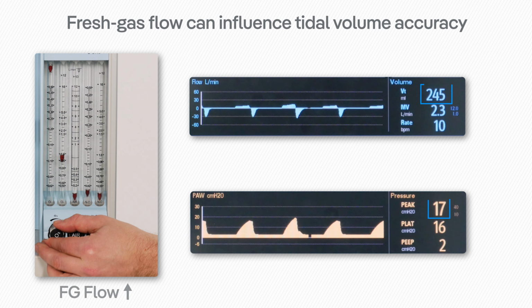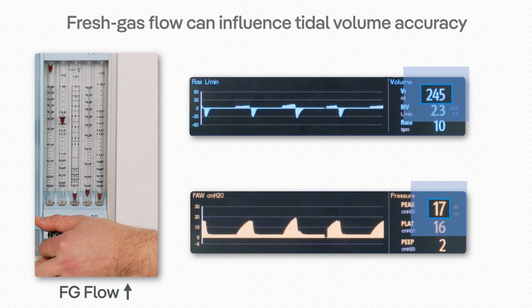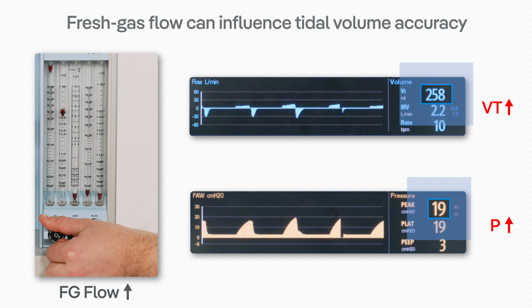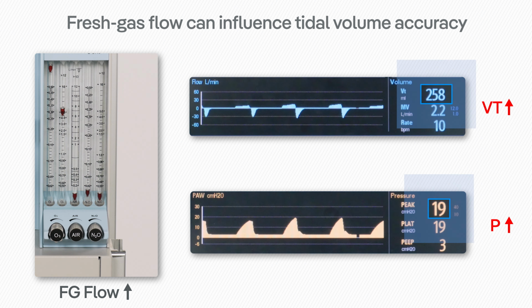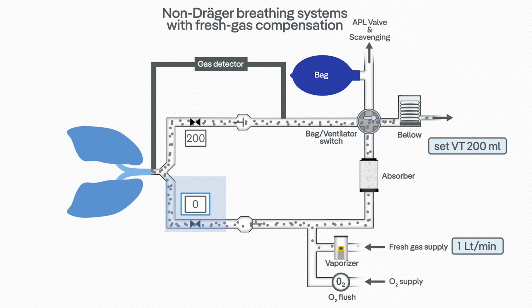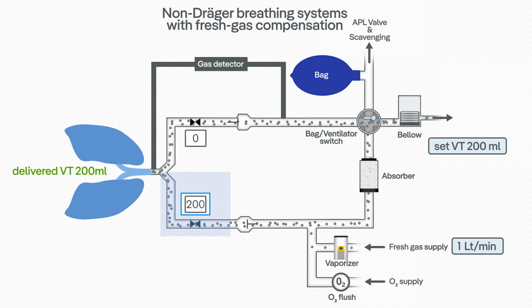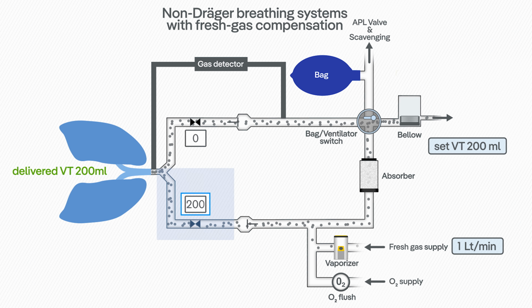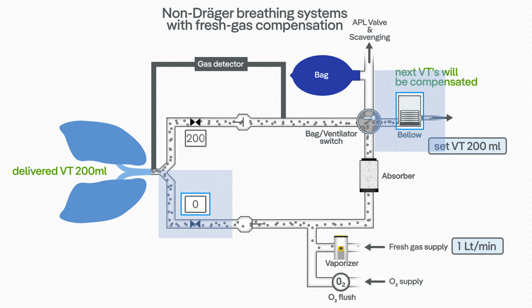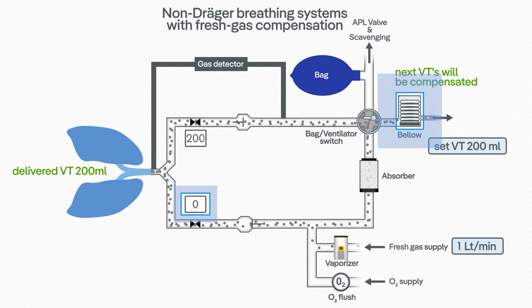Depending on the technology employed, fresh gas flow can also significantly influence the tidal volume delivery and compromise tidal volume accuracy. In some anesthesia machines, fresh gas compensation is used to eliminate this influence. With this technology, the inspiratory flow sensor is monitoring the delivered tidal volume and adjusting the ventilator accordingly to compensate for the fresh gas flow changes.